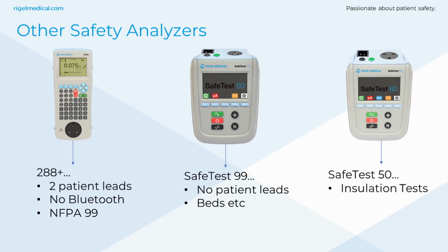The second device is a fully comprehensive device. It tests all standards, up to 10 patient leads. They can be isolated, does insulation tests. So again, that is our flagship device. It does test every single parameter that's required. But in some cases, the facility that's being worked in doesn't need such a comprehensive device.